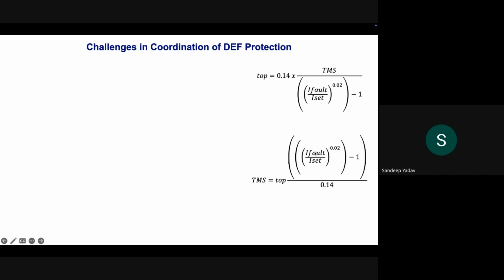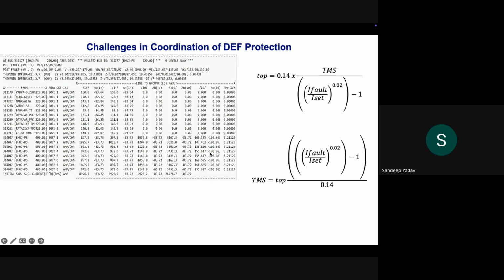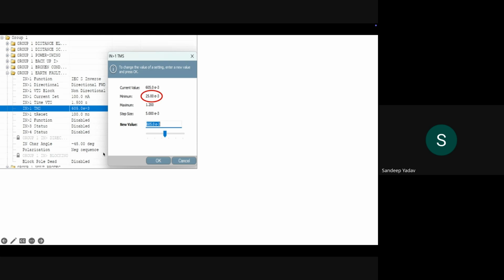You get my point. In case of RE sources, the fault contribution is not more than the rated current, so if the setting of the relay is more than the I fault, this term becomes less than 1, and less than 1 raised to the power 0.02, the entire term becomes less than 1. If we subtract 1 from a term which is less than 1, this becomes negative. So TMS becomes negative. Now the problem is that in all kinds of numerical relays, or for that matter even electromechanical relays, you cannot set a negative TMS, because negative TMS does not make sense physically. Time cannot be negative. Operating time can only be positive.